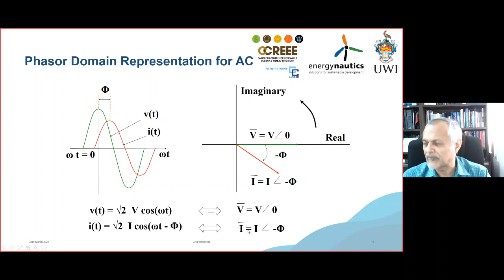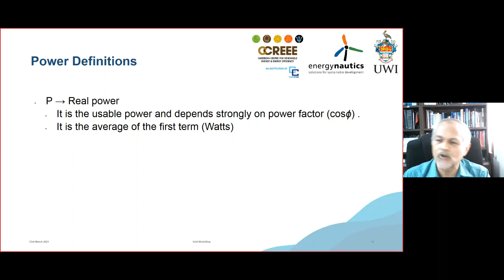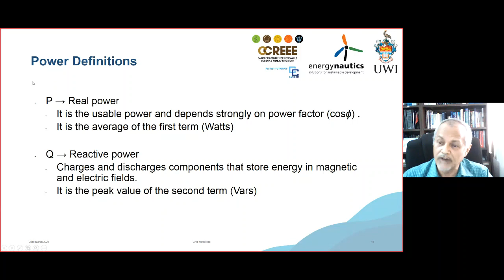Now my power definitions. Real power is the usable power, the power that actually does work, and it depends strongly on the power factor in its equation; it's measured in watts, kilowatts, or megawatts. Reactive power is a requirement inherent in any AC system, having to do with the electromagnetic and electrostatic charging and discharging of the inductors and capacitors on the power system. So P and Q are what we have. We cannot get rid of Q; it's an inherent property of all AC systems. However, the only power that actually does work is P.